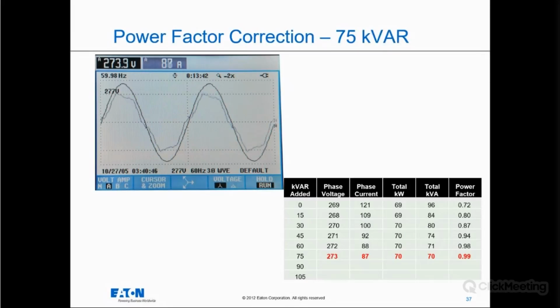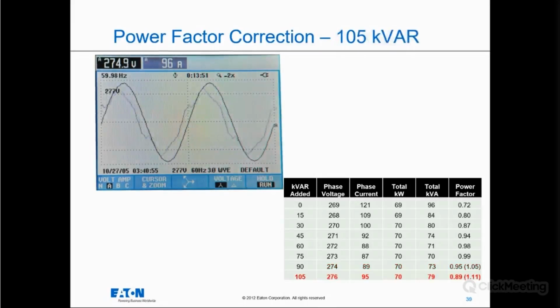But what happens if we bring on another 15 kVAR? You can see now our waveforms up top are almost in phase. What's going to happen is we're going to cross over from an inductive circuit to a capacitive circuit. So we're going to have the same problem as we keep adding capacitors into this circuit. You can see that we now are consuming more kVA and more phase current in the capacitive circuit. So we are leading, what would be referred to as capacitive leading.